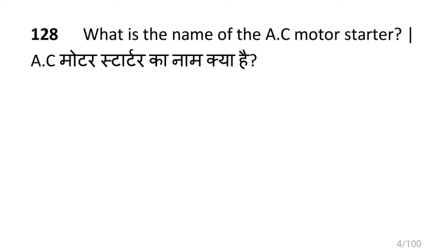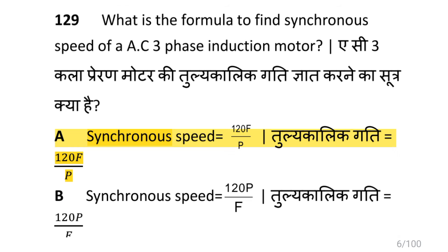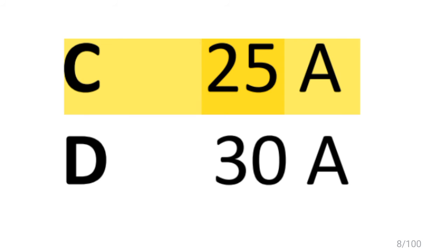The name of the AC motor starter is the auto transformer starter. The formula to find synchronous speed of an AC three phase induction motor is: synchronous speed equals 120F divided by P. The fuse rating to run a 10 HP three phase induction motor at full load is 25A.